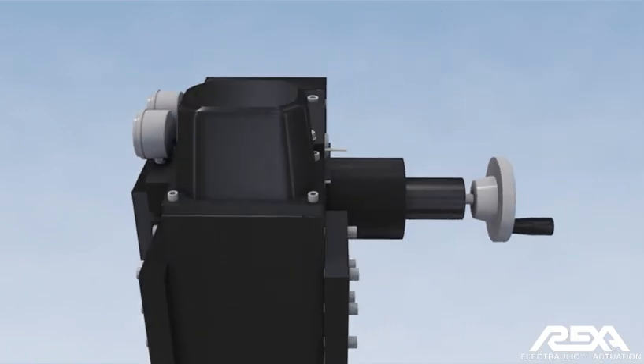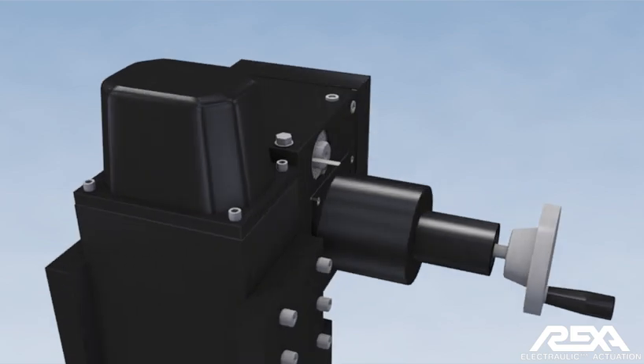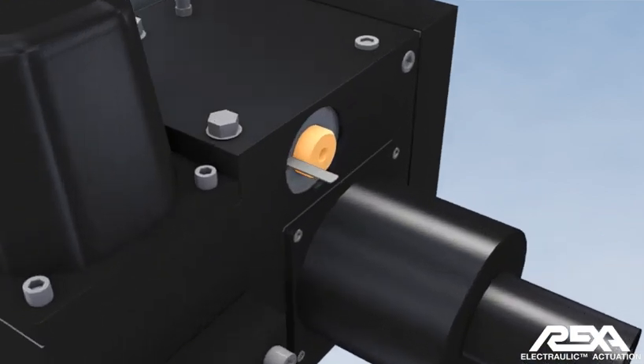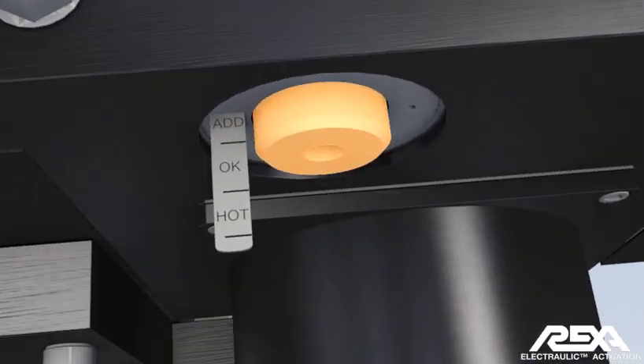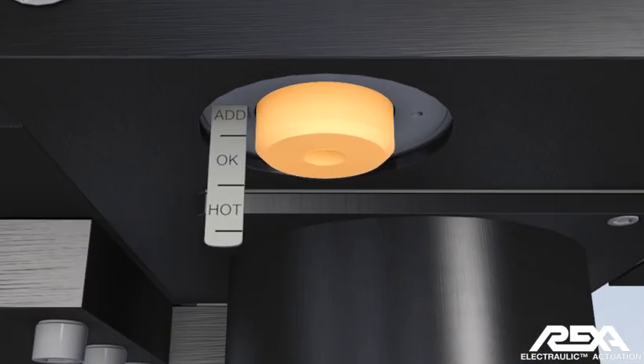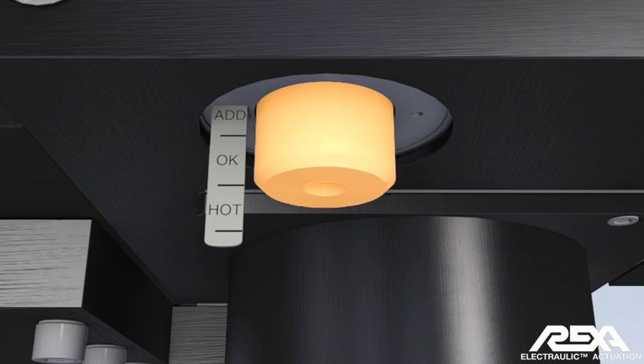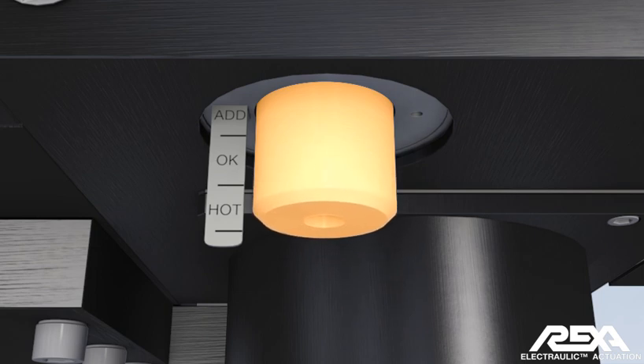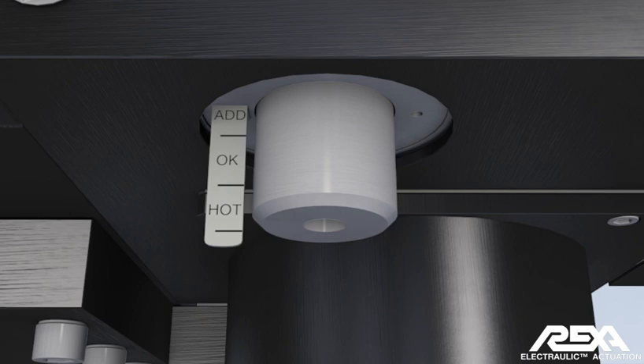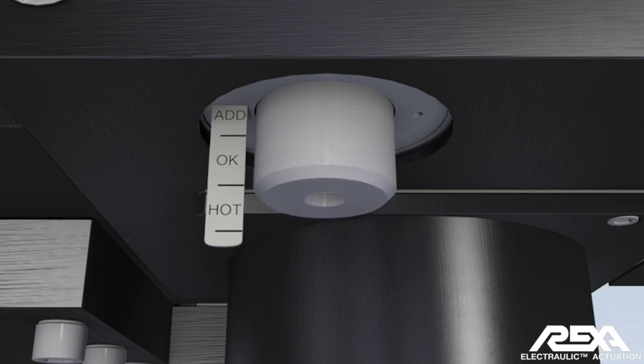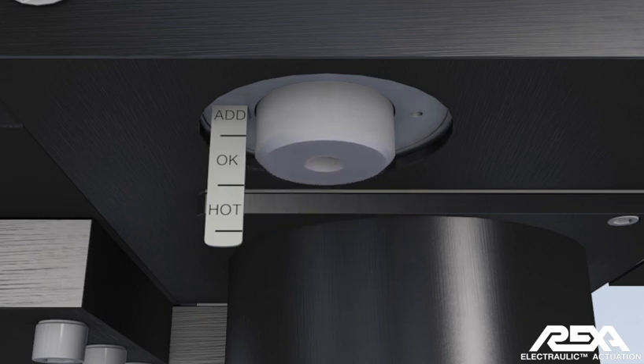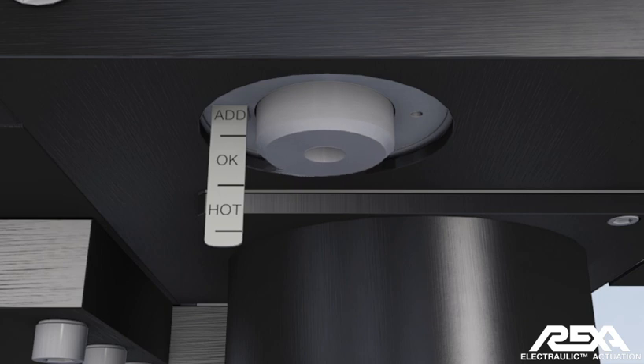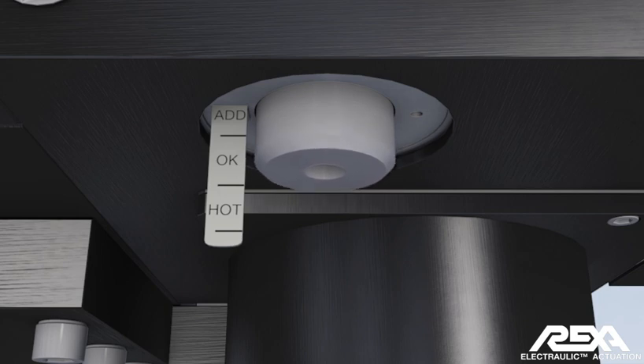The REXA actuator contains a thermal expansion chamber that provides an auxiliary volume for expansion and contraction of oil as it heats or cools, depending on plant environment and operating conditions. The spring-loaded oil level indicator moves in and out along a level scale to identify the system oil level.